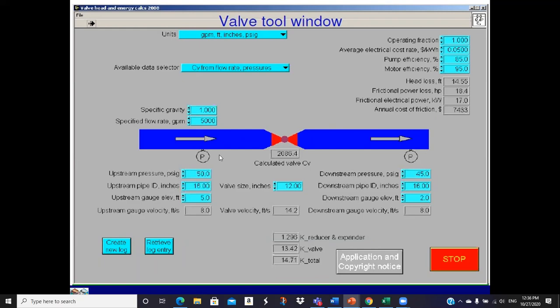We put in our pipe diameter. So I've got 16 inch here, 16 here. And it's very common for a valve to be sized a little smaller than the piping. It gives it what they call more authority, more bite. When that valve starts closing, it has more impact on the flow. If the valve is too big, you might have to close it 50% before it really affects the flow. So if you downsize the valve a little bit, you have a larger pressure drop when it's open, but when you start closing the valve, it actually does something, you get a change in flow at 90%, 80%. If the valve is sized the same as the pipe, you may have to close it to 70 or 60% before you do anything. And so you lose controllability. They call that authority in the control world, I believe.